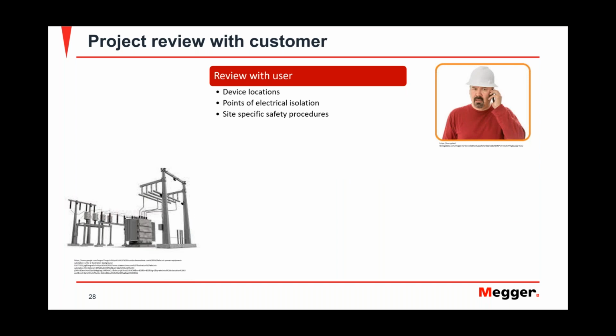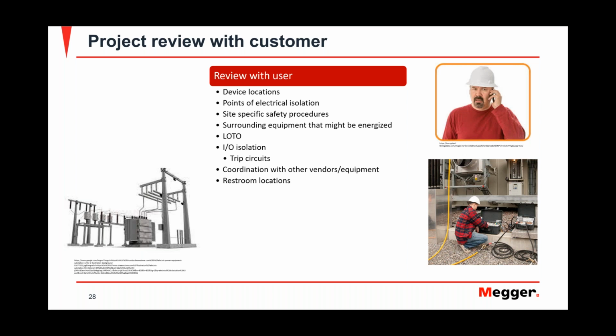Once you're with the customer, what to review: the physical device locations, my isolation points. Now walk them through with the customers. Don't just assume that you looked at them in the diagram, in the drawings, and that you know where it is. One thing is looking at the drawing. Another thing is seeing the device in real life, seeing that everything is locked out, tagged out, physically seeing the switches open. Be aware of your surroundings.